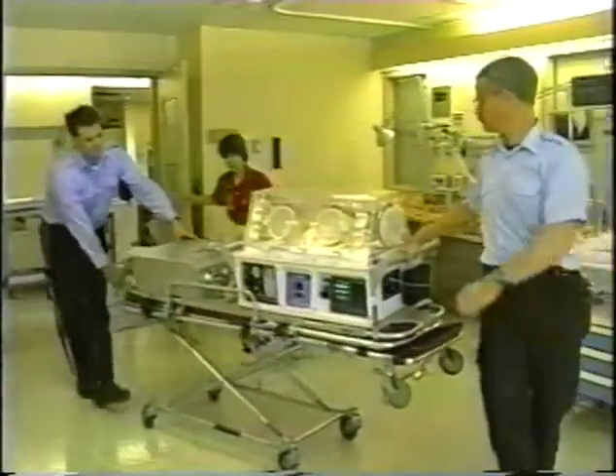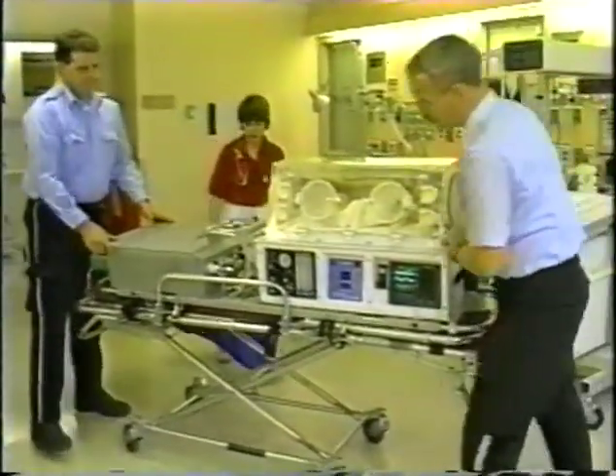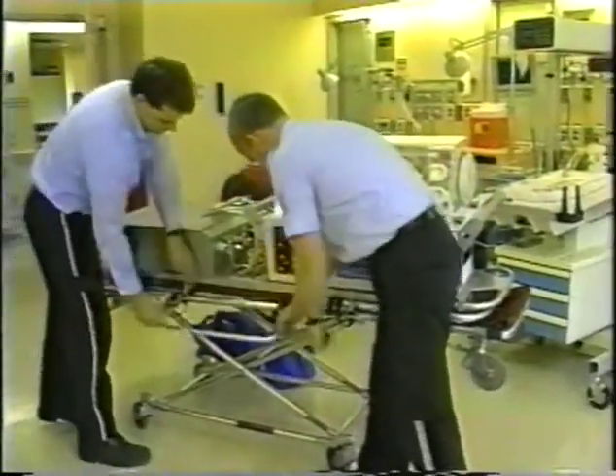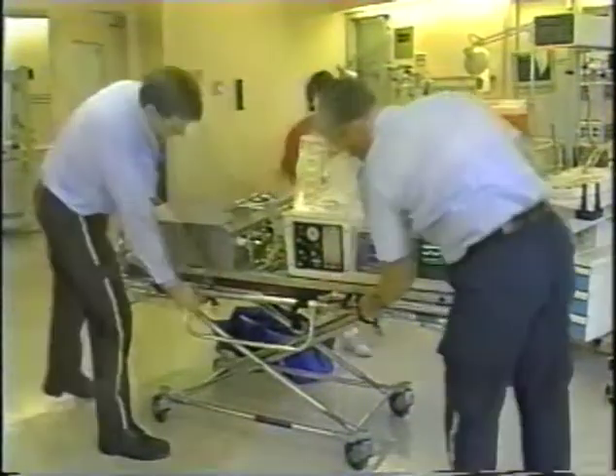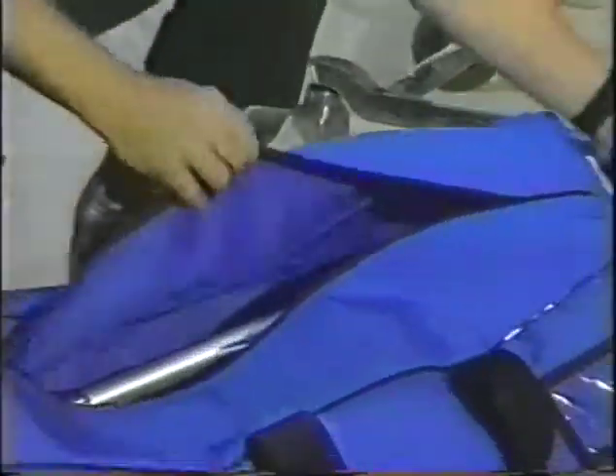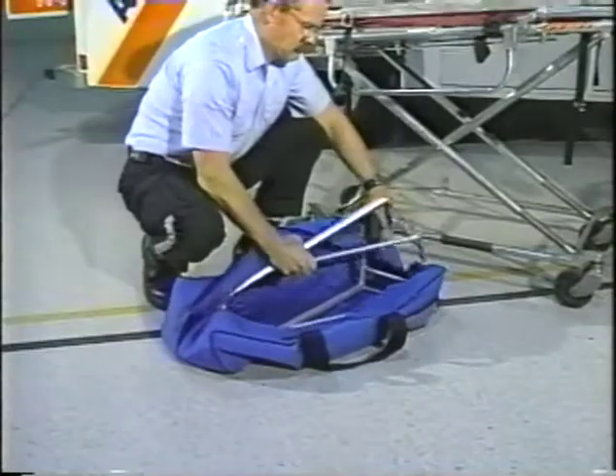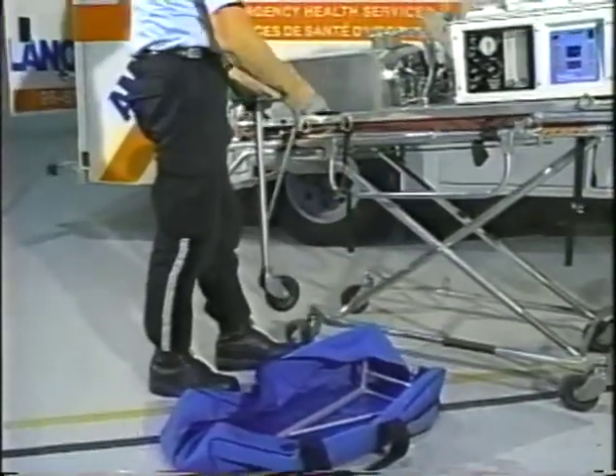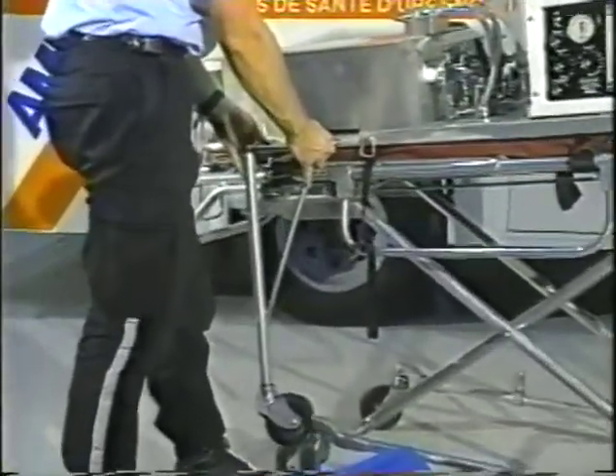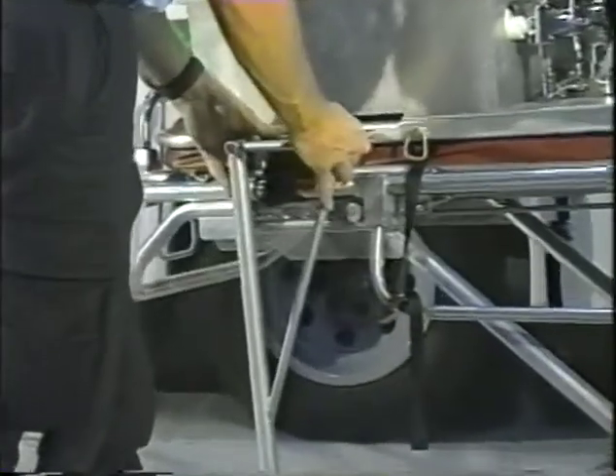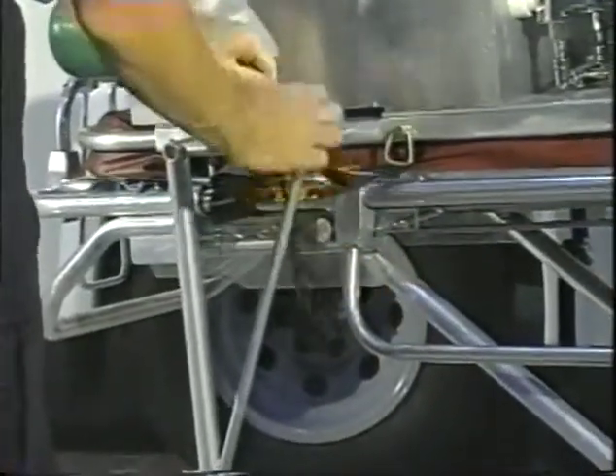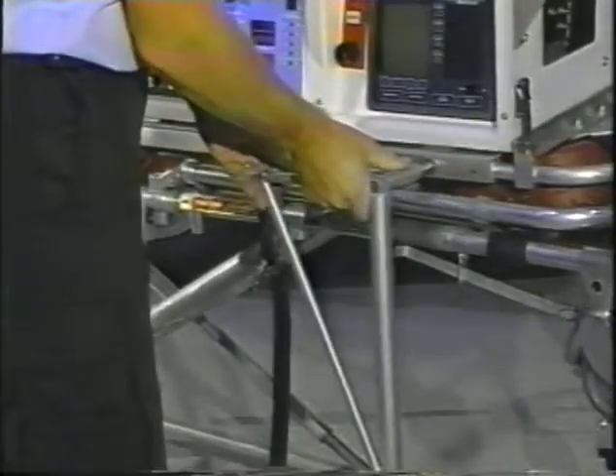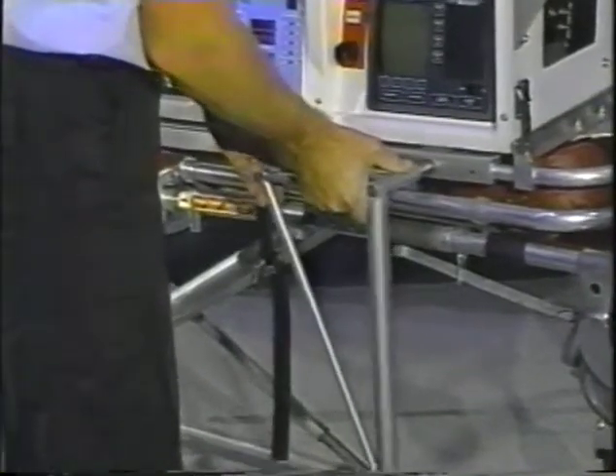Once in the neonatal unit, undo the 4 safety straps securing the incubator deck to the 35A. Remove the wheel and leg assembly from the carrying bag. Note that there are different configurations for the head and foot ends of the incubator adapter deck. Insert the 4 leg and wheel assemblies into their receptacles on the adapter sides, ensuring the pins are fully inserted.